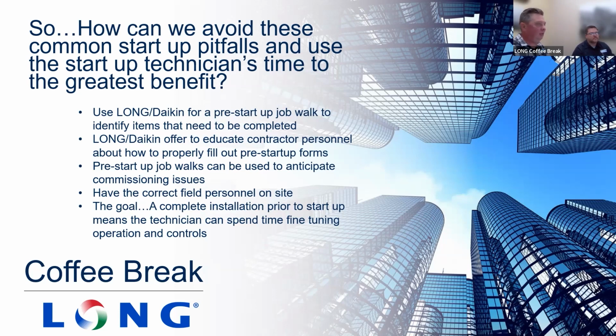Yeah, absolutely. So what are some of the pitfalls of starting up a piece of equipment before the building is ready? The equipment doesn't care if I have doors and windows, does it? Why would you care? Right. So the reason I care is because you're going to want that unit to run to maintain duct static. If there's nothing there to create resistance against that duct, like windows and doors, then we're not tuning it to the duct static that is necessary.